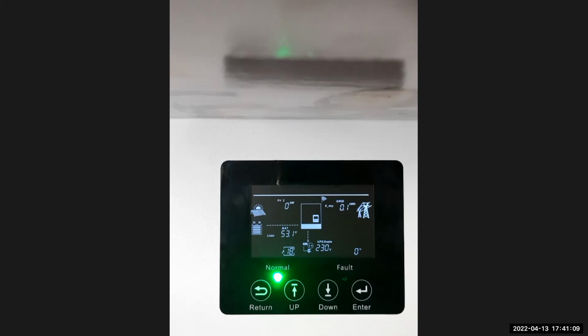18 is for generator in. You can tell it what's the amount of power that it can take from the generator. Let's say 2 kilowatt. We're happy with 2 kilowatt. So that's that. Okay, this function here. This is the function when you have PV panels but no battery. You can technically run this unit without any Eskom and battery, only on PV power.